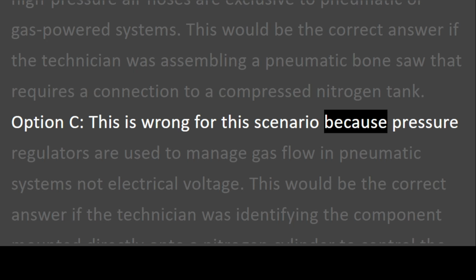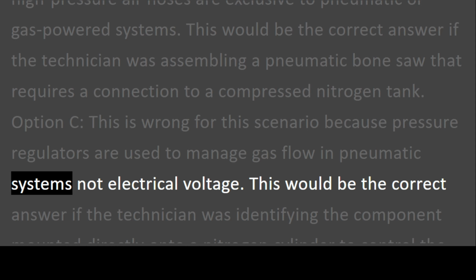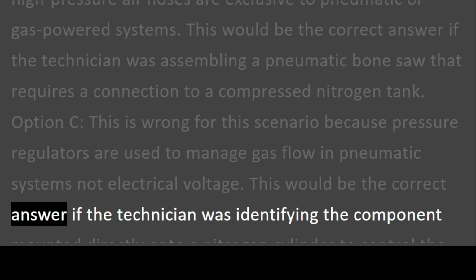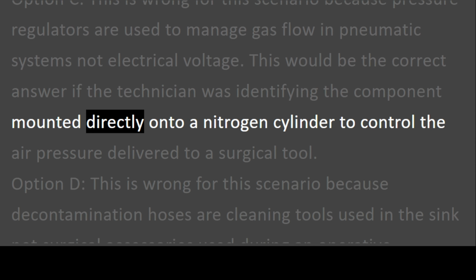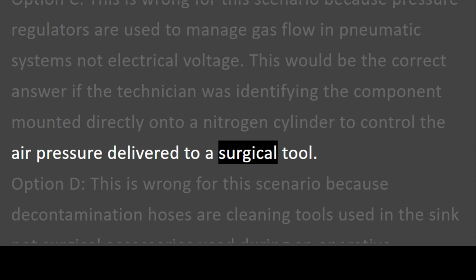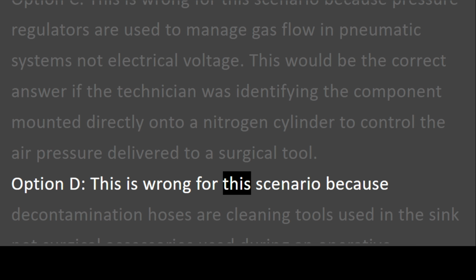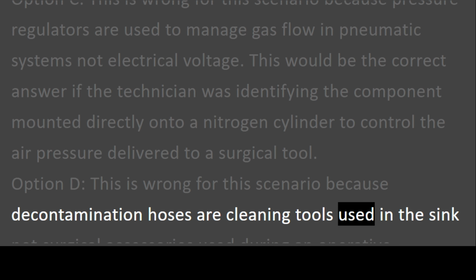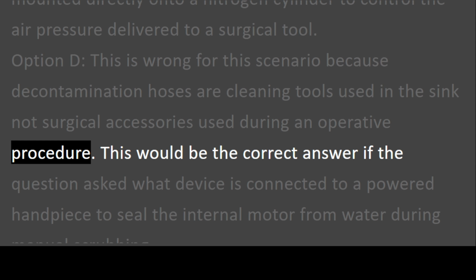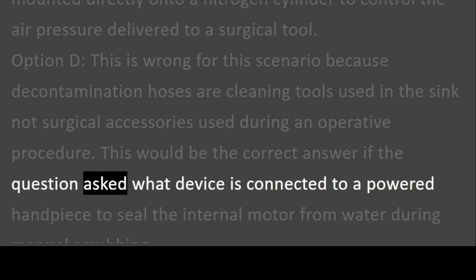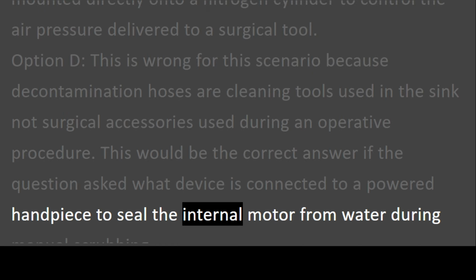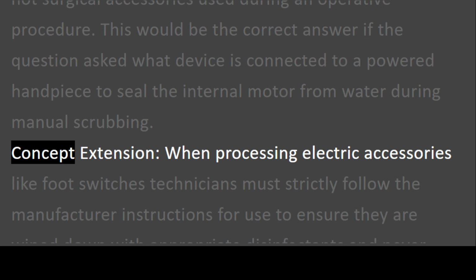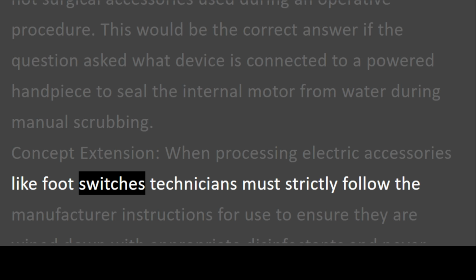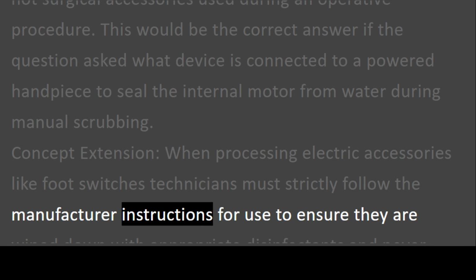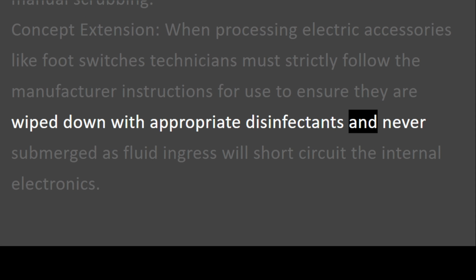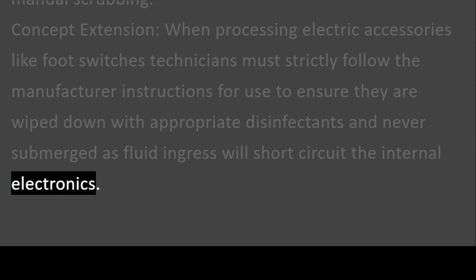This is wrong for this scenario because pressure regulators are used to manage gas flow in pneumatic systems, not electrical voltage. This would be the correct answer if the technician was identifying the component mounted directly onto a nitrogen cylinder to control the air pressure delivered to a surgical tool. Option D. This is wrong for this scenario because decontamination hoses are cleaning tools used in the sink, not surgical accessories used during an operative procedure. This would be the correct answer if the question asked what device is connected to a powered handpiece to seal the internal motor from water during manual scrubbing. Concept extension. When processing electric accessories like foot switches, technicians must strictly follow the manufacturer instructions for use to ensure they are wiped down with appropriate disinfectants and never submerged, as fluid ingress will short-circuit the internal electronics.